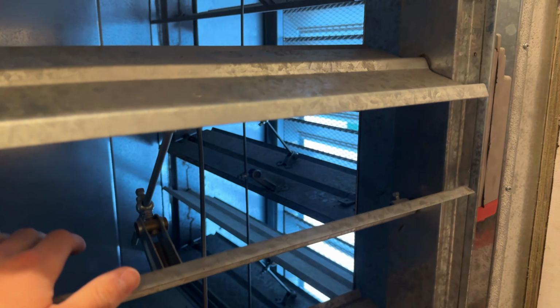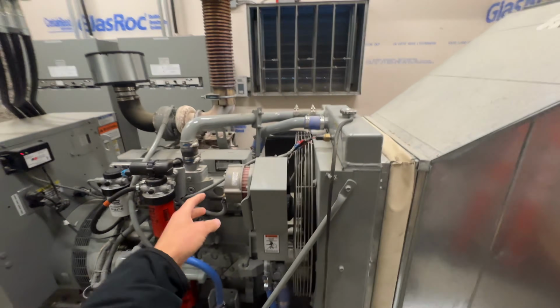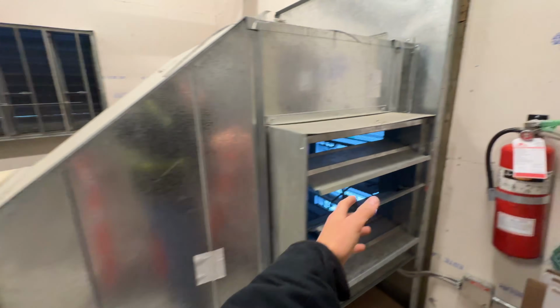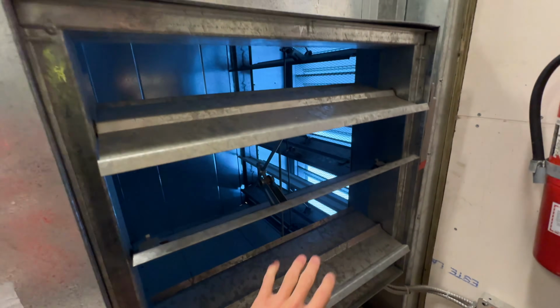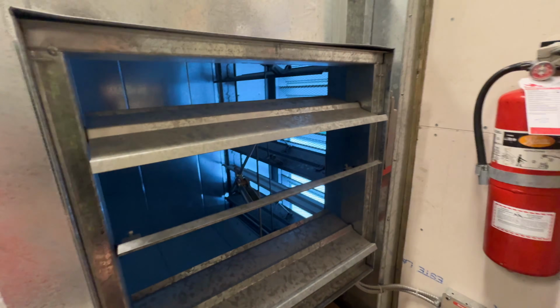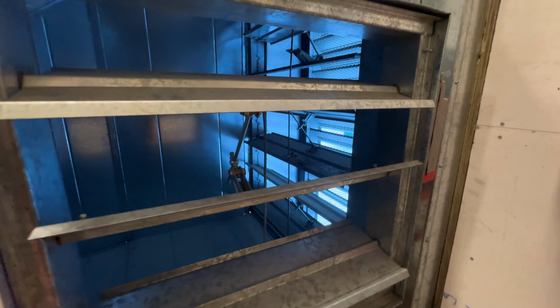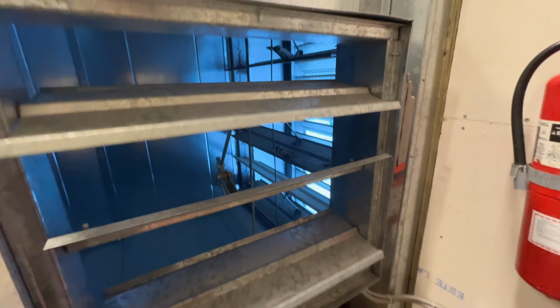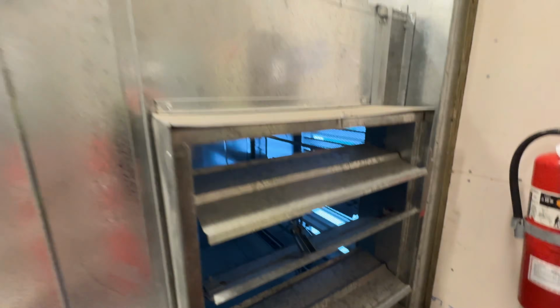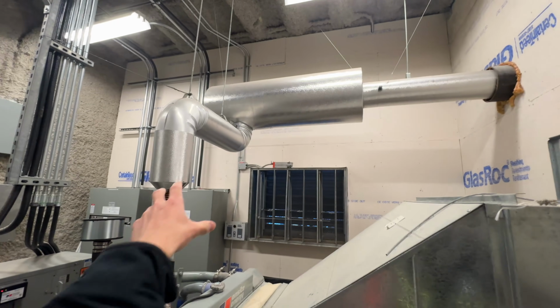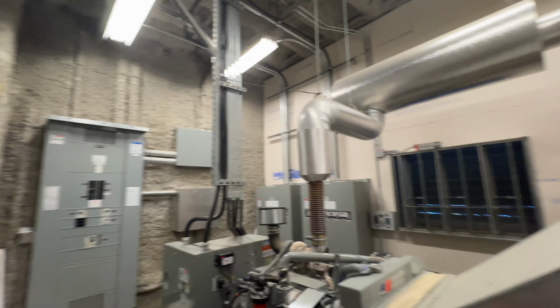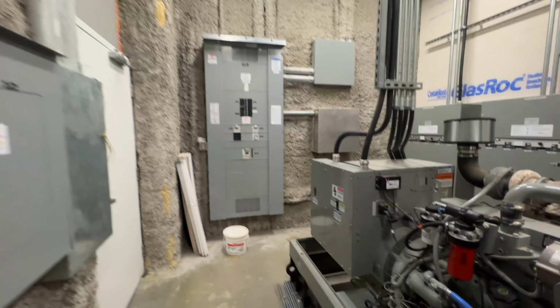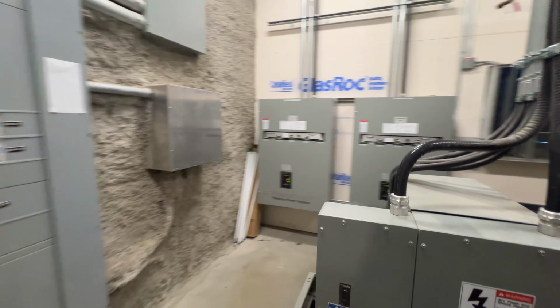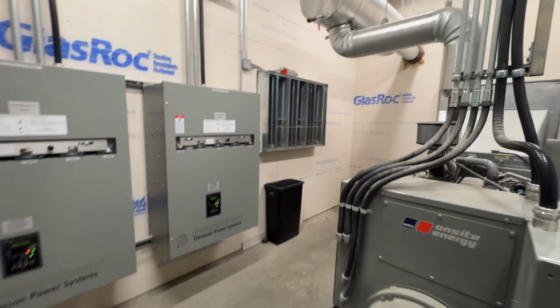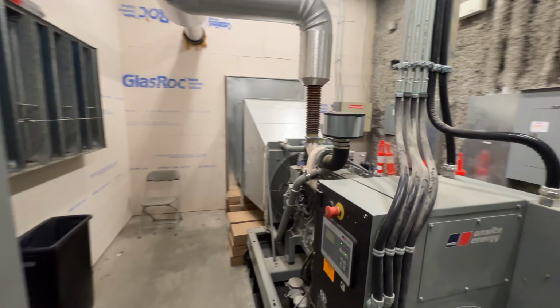This is where air is coming over the radiator. I believe it's pulling the air in through there, over the radiator, out the building here. And this will open up or close depending on room temperature, I think. Not exactly sure what this damper is doing here. But we can go look at this from the outside and see where the diesel exhaust goes to the outside of the room. It's really noisy in here anyway, so I want to limit my exposure to the high level in here.